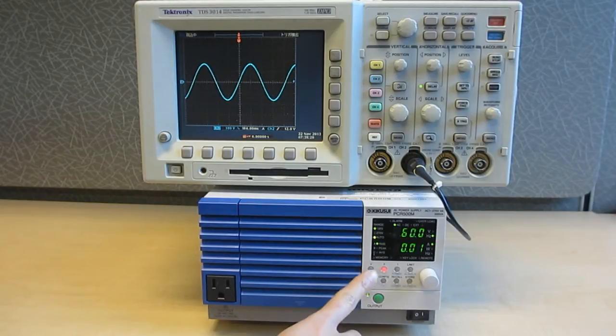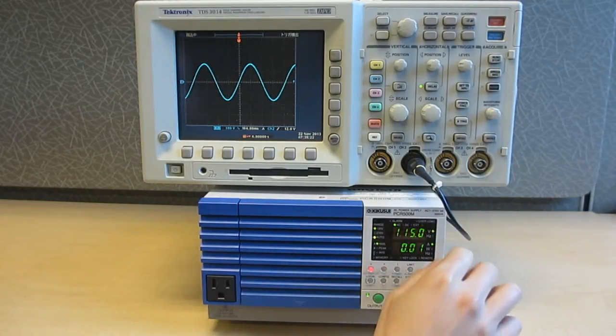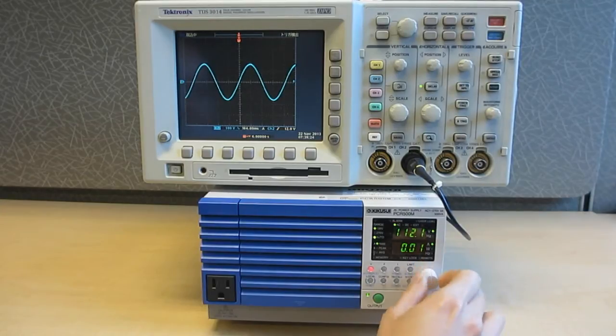Now we can also vary the output voltage and frequency around these levels for margin testing. These can be seen changing on the oscilloscope.